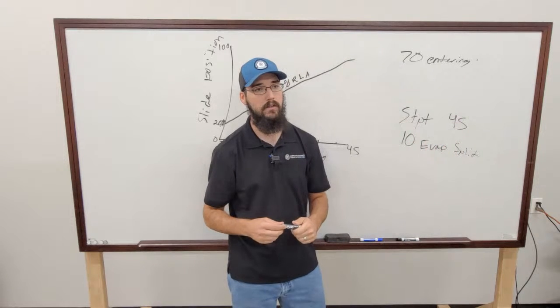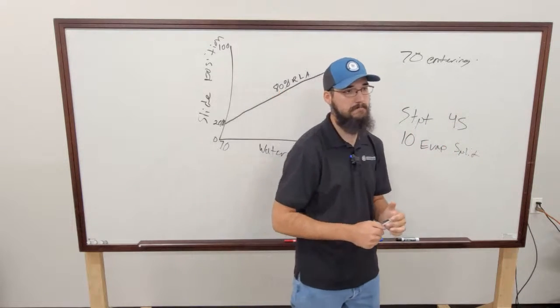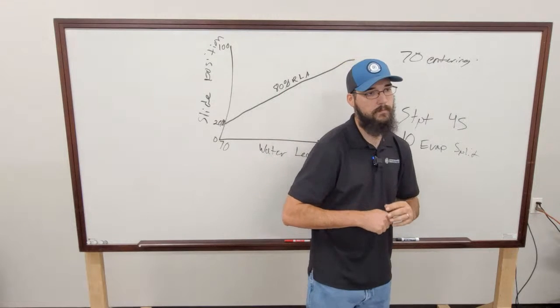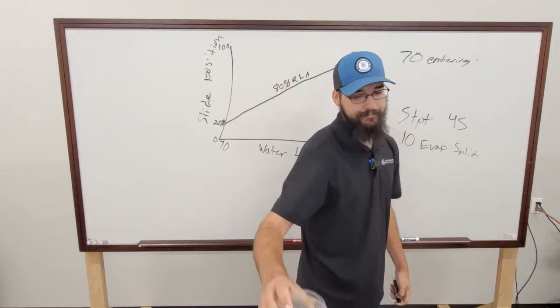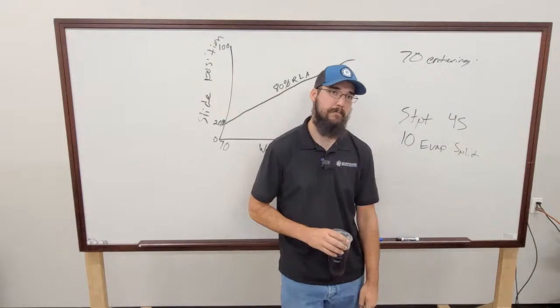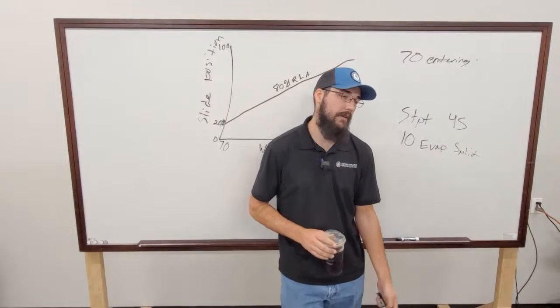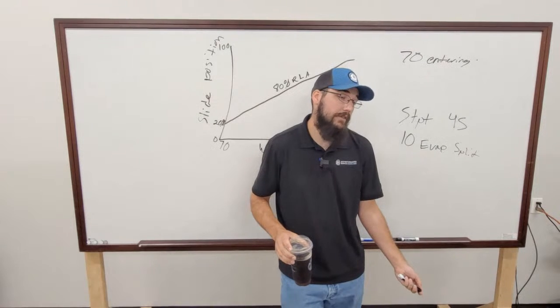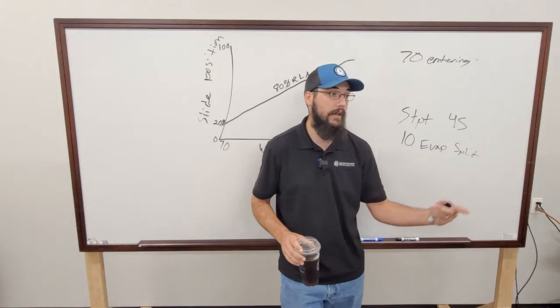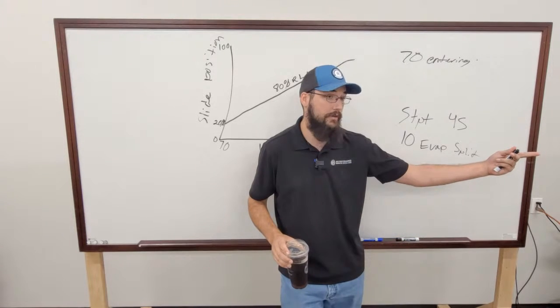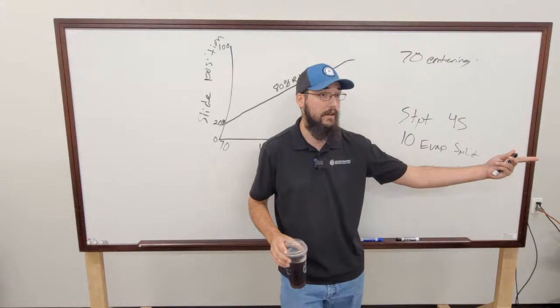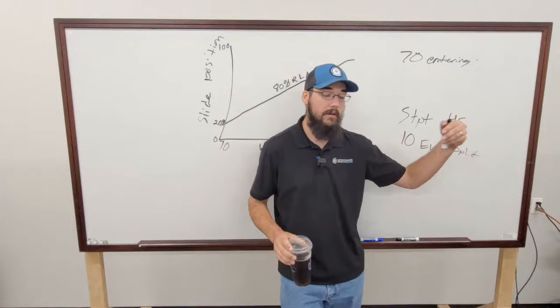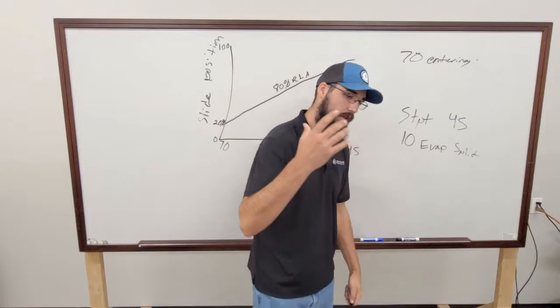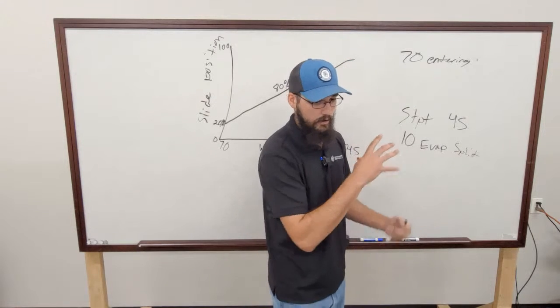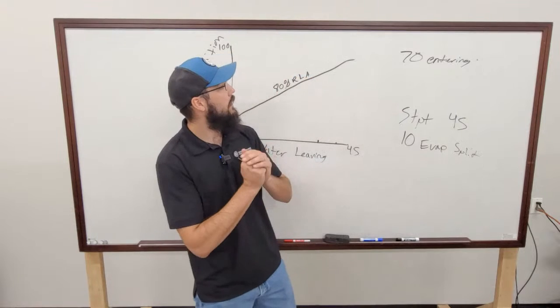Would that be because it's not supposed to be doing that all the time, so they're kind of willing to go past that threshold for just a little bit until they get down to what it was actually designed for? Genuinely, I'm not 100% sure, because in a real case scenario, it can push that and run at 105, 110% RLA for an extended period of time. Especially if it's, because this gets into staging and the whole loading, and I'm getting a little bit ahead of myself.